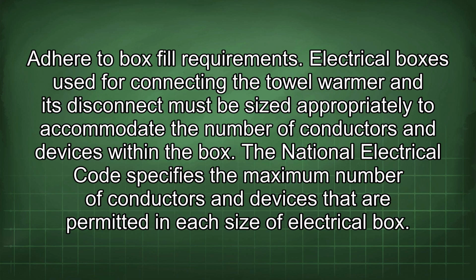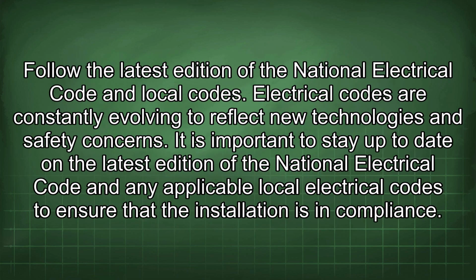Adhere to box fill requirements. The electrical boxes used for connecting the towel warmer and its disconnect must be sized appropriately to accommodate the number of conductors and devices within the box. The National Electrical Code specifies the maximum number of conductors and devices that are permitted in each size of electrical box. Follow the latest edition of the National Electrical Code and local codes.